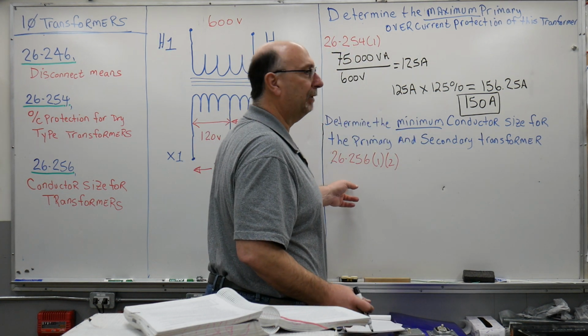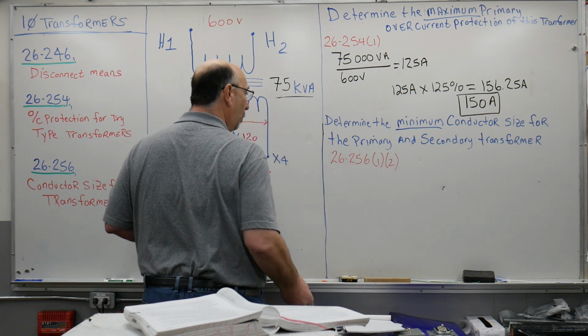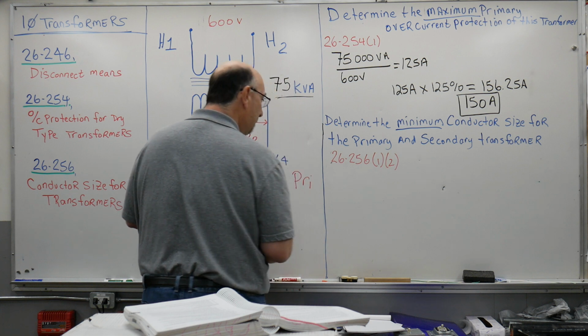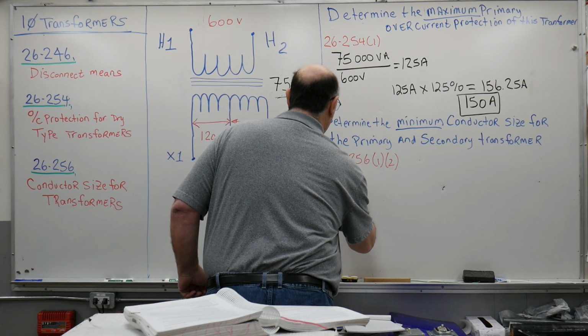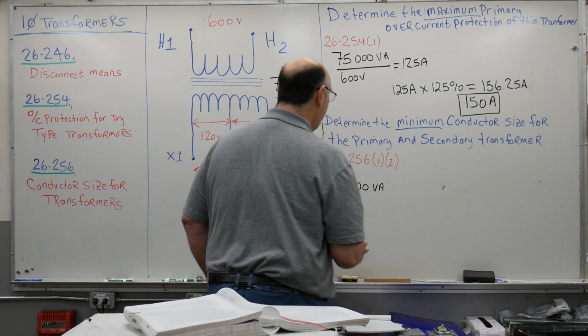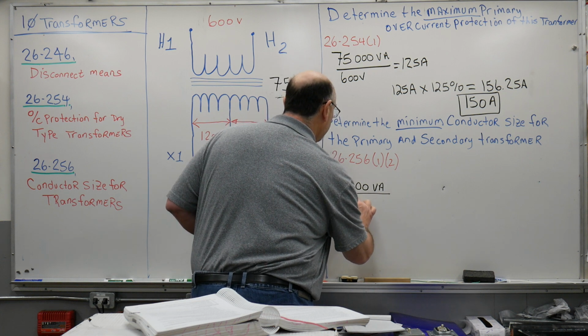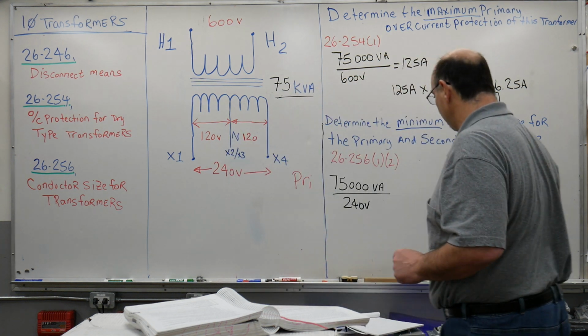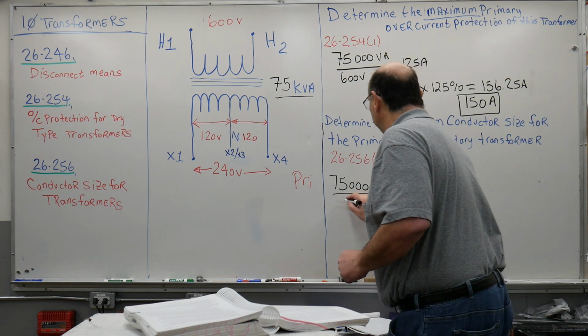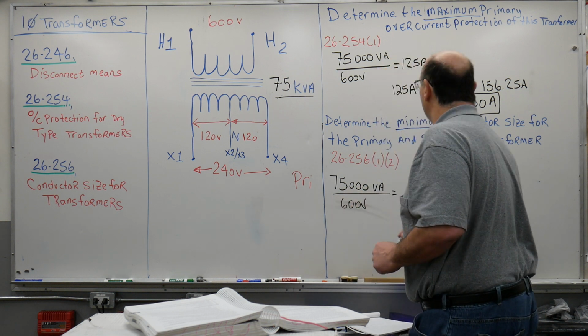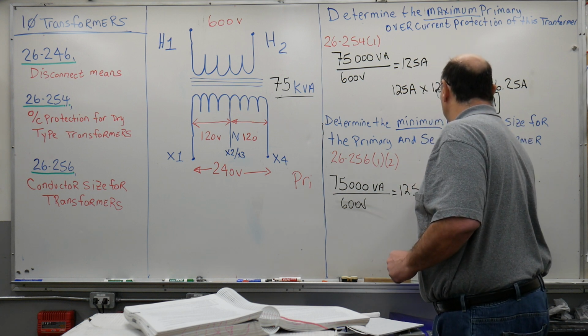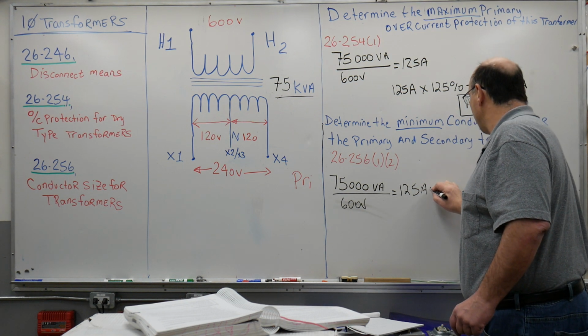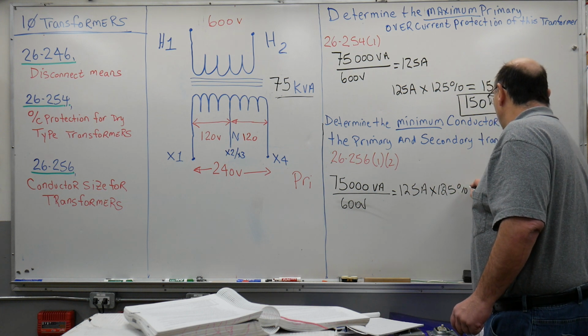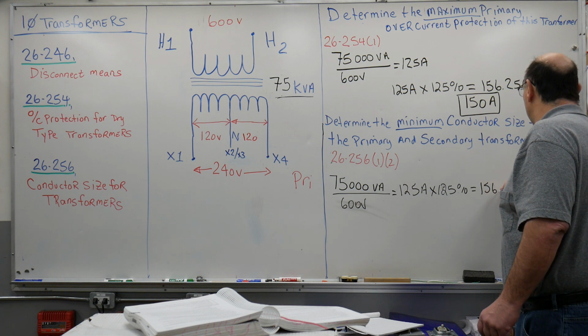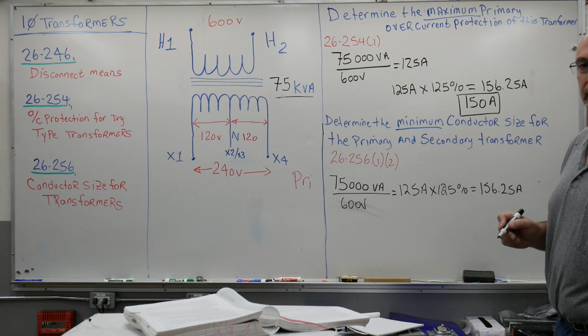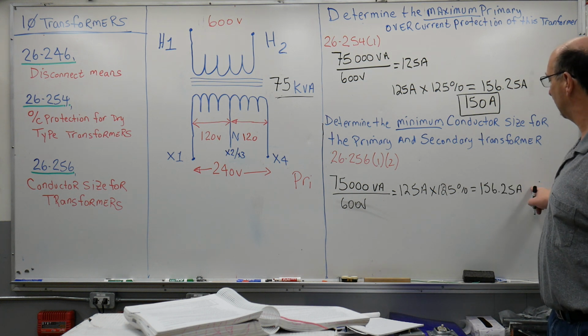Next, we have to determine the minimum conductor size. So once again, we're going to work with the primary first. Once again, 75,000 VA divided by 240 volts. Oops, wrong. Too early in the morning. 600 volts. And once again, 125 amps. We throw in the safety factor of 125%. And lo and behold, we come up with 156.25 amps. That is our minimum primary conductor ampacity.